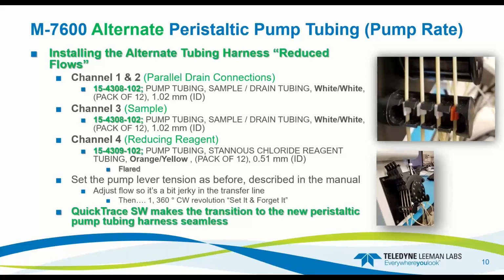The reducing agent, the stannous, is a little bit thinner tubing, smaller OD and ID, so you turn that in about 1 millimeter further. And once you set it, you forget it. You never want to mess with the tension for failing pump tubing. Only change the tubing harness and leave the tension the same. And with that, typically we'll break in the peristaltic pump tube for about an hour with DI water and reagent.